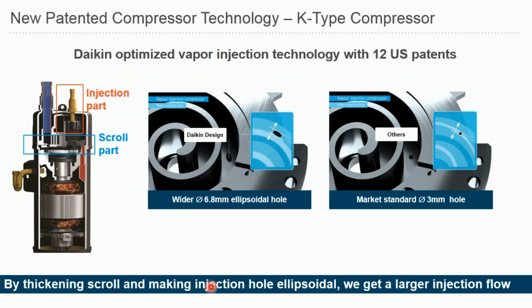So let's remember how the K-type compressor is different compared to other vapor injection compressors that you see in the marketplace. Daikin is not the only VRV or VRF manufacturer that uses vapor injection technology on the compressor side, but it took us a while to come up with a new compressor design, because we didn't think the compressor options out there in the marketplace were on par with Daikin standards from an energy efficiency and reliability standpoint, and that's why it took our engineers a while to develop something new. And keep in mind, the compressor is designed and engineered by Daikin, so we're not buying this compressor from a third-party manufacturer.